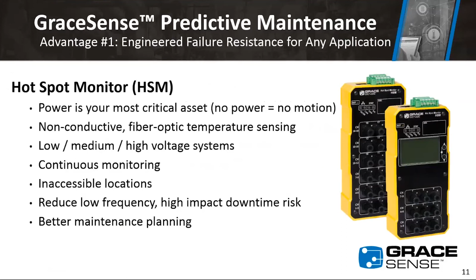Here's a bit of how it works. The hotspot monitor module sits in the low voltage compartment, and you route these 15-meter polymer fibers to the connection, bolted down at the bus bar or circuit breaker lug, whatever you have there. We send an LED pulse down the fiber, and there's a phosphor tip on the end which detects temperature and reflects it differently based on the temperature, read back at the head module.